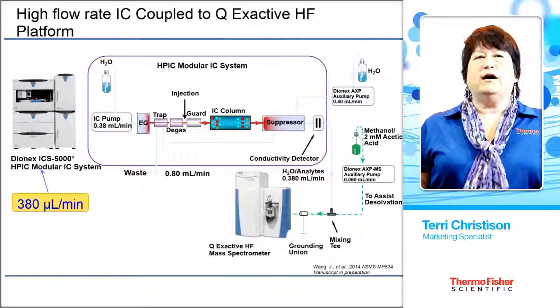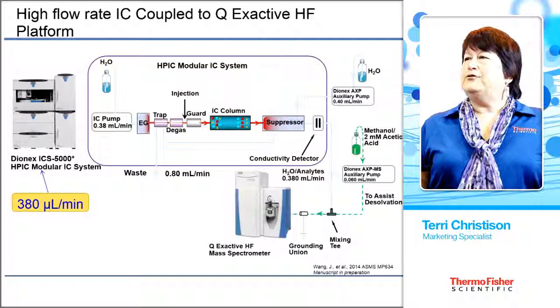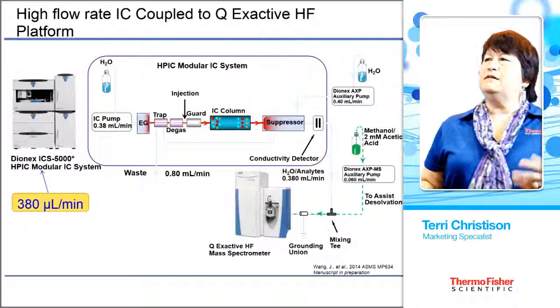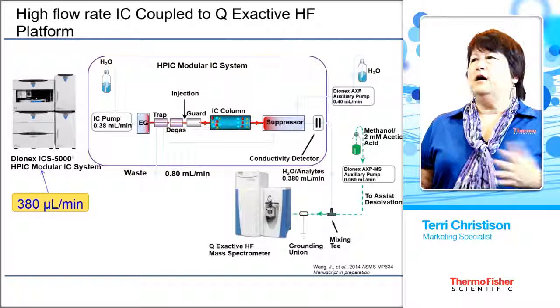The desalting suppressor is what makes it possible to couple the IC with the mass spec. In-line is our first detector — we're using a conductivity detector to monitor the health of the suppressor. After that, the effluent from the conductivity cell is coupled with a makeup solution of methanol and acetic acid, or you can just use methanol, and it's introduced into the mass spec. These electrolytic devices require a backflow of fluid to drive the chemistry, so since we're using the effluent to go to the mass spec, we introduce water to drive those reactions.